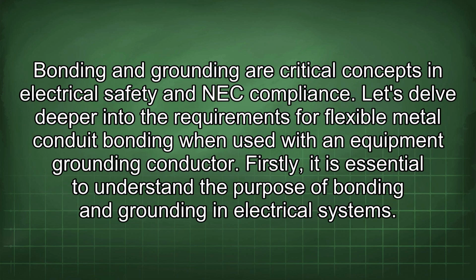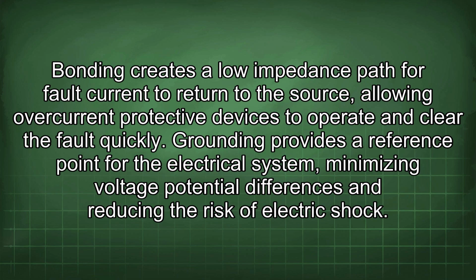Bonding and grounding are critical concepts in electrical safety and NEC compliance. Let's delve deeper into the requirements for flexible metal conduit bonding when used with an equipment grounding conductor. Firstly, it is essential to understand the purpose of bonding and grounding in electrical systems. Bonding creates a low impedance path for fault current to return to the source, allowing overcurrent protective devices to operate and clear the fault quickly. Grounding provides a reference point for the electrical system, minimizing voltage potential differences and reducing the risk of electric shock.